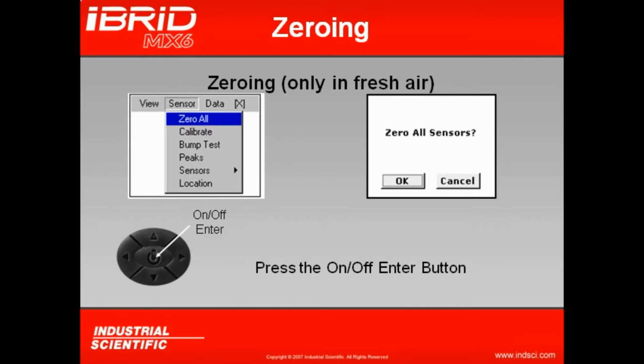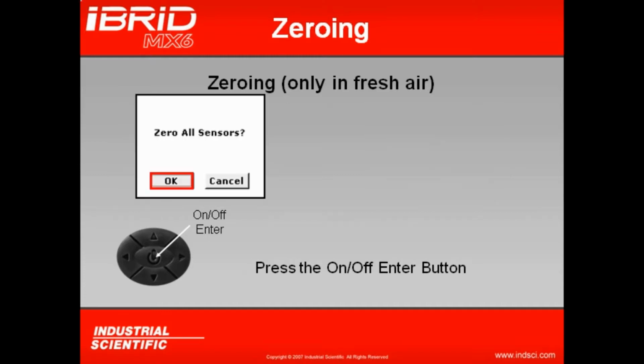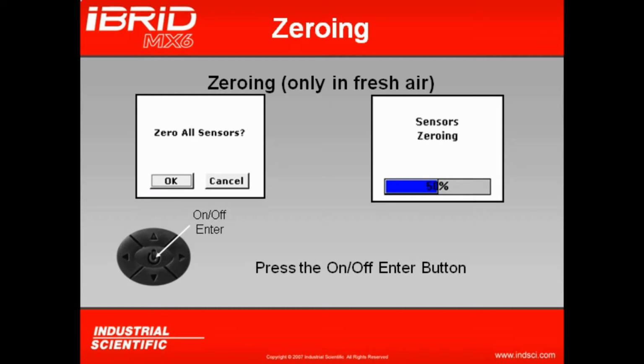At this point, it's going to ask me if I truly want to zero all of my sensors. Clicking OK will start the zeroing process automatically. The first thing the instrument will do is take my toxics and combustibles and set them to 0, eliminating any type of negative drift.